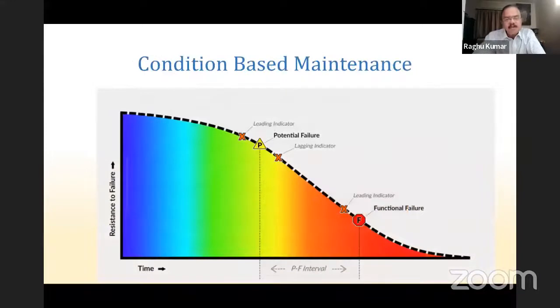stage, which is explained in this PF interval graph. It's a potential failure to functional failure. In the first stage, the transformer is healthy, and then it starts developing a problem somewhere here, and it starts giving you leading indicators. It is like your pre-diabetic stage. You are not diabetic, but you have started getting symptoms that you are going to be. And then this is the point where the potential failure starts. Later on, you get a higher level of signals. So you have to catch this period. Within this time, the maintenance has to be carried out. If you don't do anything, it will lead to a failure at this point of time. So this is the principle of condition-based maintenance.